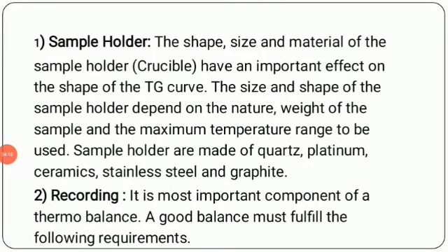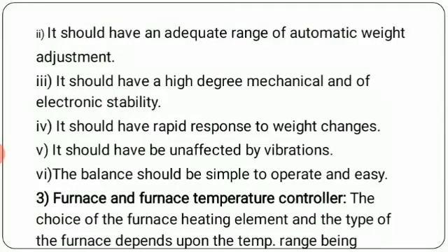Second component, the recording balance. It is the most important component of the thermobalance. A good balance must fulfill the following requirements. First, its accuracy, sensitivity, and capacity should be similar to an analytical balance. It should have an adequate range of automatic weight adjustment.